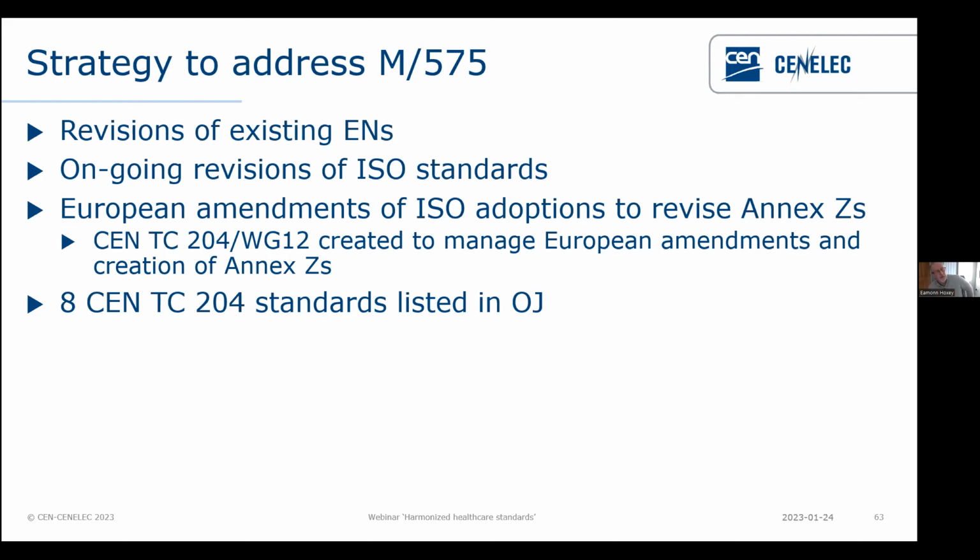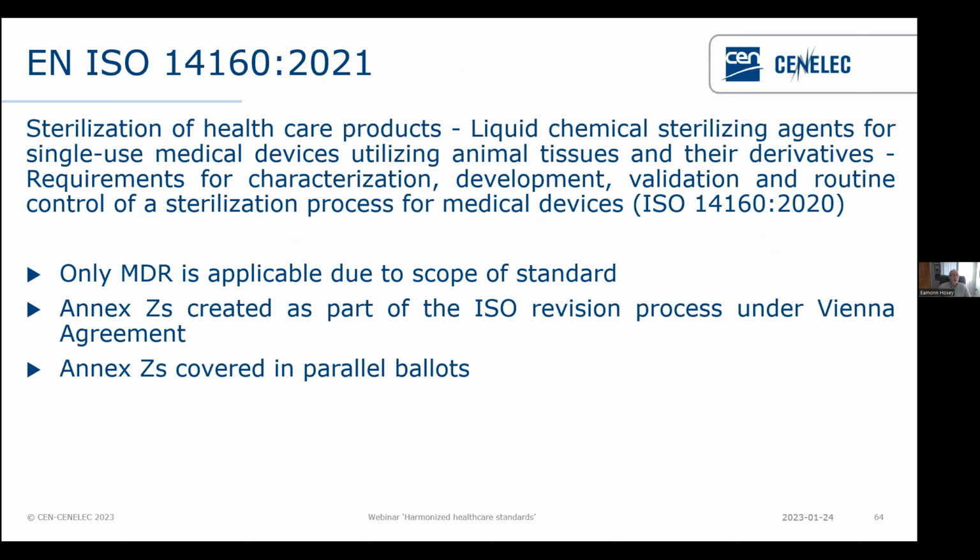We currently have 8 of our standards listed in the OJ as providing a presumption of conformity against the MDR, and 7 of those are also listed for the IVDR as well. So we just wanted to use one example of those standards, and that was the adoption of EN ISO 14160, dated 2021.